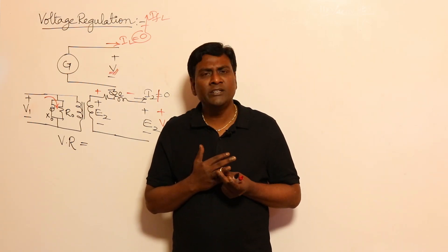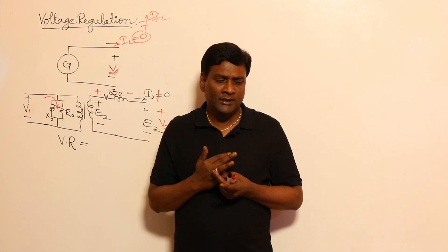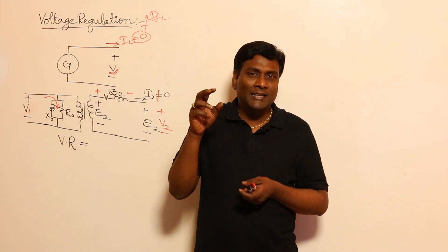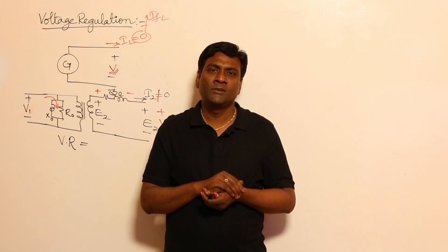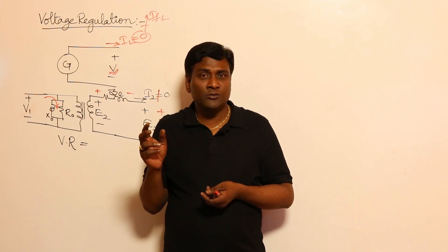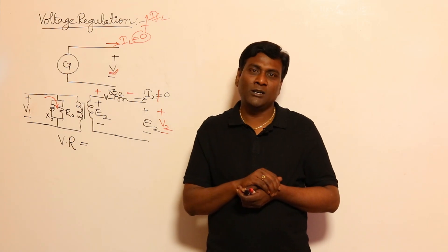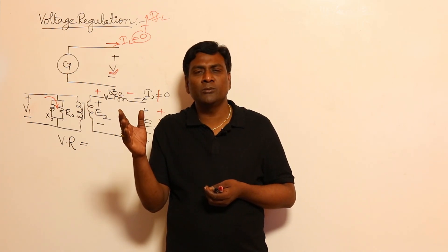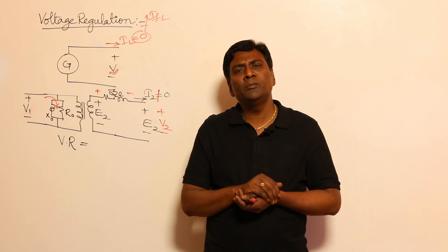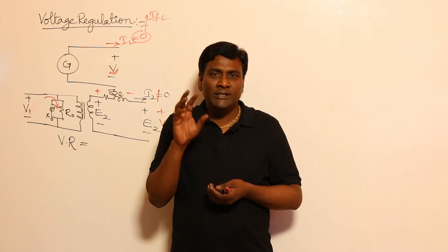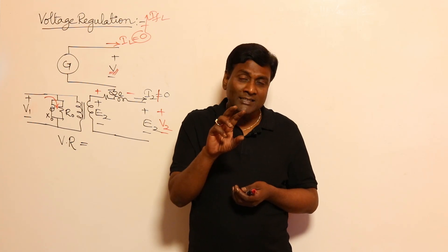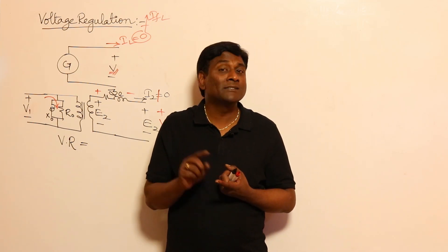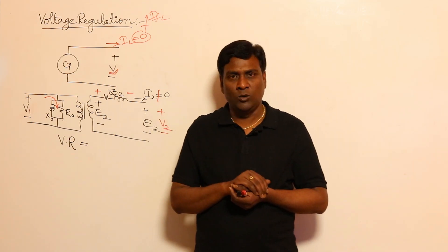There is an important distinction between distribution transformer and power transformer. In a distribution transformer, loads are directly connected — for example, the supply coming to your home comes from a distribution transformer. That output voltage is going to vary: if you switch on your AC, that load appears on the distribution transformer; if you switch it off, that load disappears. So the load component of current I2 and the power factor angle θ2 are both decided by the connected load.